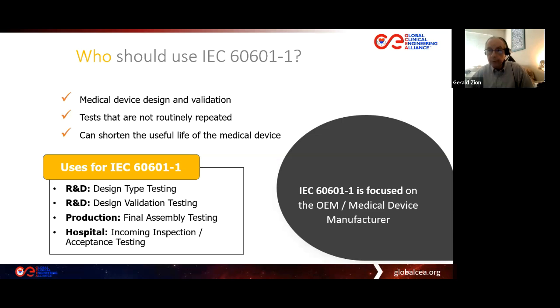So design, validation, and type testing, final assembly testing in the factory, and then on incoming inspection, we may choose to use IEC 60601-1, or we may be directed and required by the manufacturer to use IEC 60601-1 as opposed to any other standard for the purpose of that acceptance test. And the reason that they would do that is because it allows them to track the testing results measurement by measurement, parameter by parameter, the way that it left the factory. So they want to make sure it arrived at your site with the same quality that it was shipped from their location.